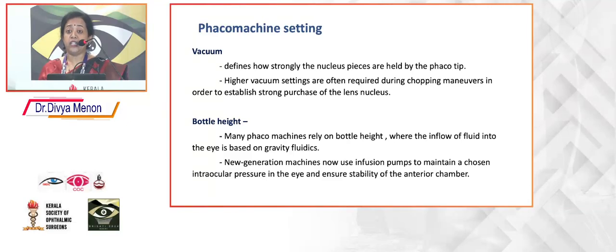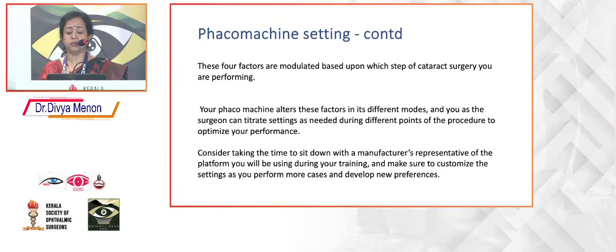Vacuum defines how strongly the nucleus pieces are held by the phaco tip. Higher vacuum settings are often required during the chopping maneuvers in order to establish a strong purchase of the lens nucleus. Many phaco machines rely on bottle height, where the inflow of fluid into the eye is based on gravity fluidics. So depending upon the cataract and depending upon the eyes, you have to adjust your bottle height. Newer mid-generation machines now use infusion pumps to maintain a chosen IOP in the eye and for anterior chamber stability. So these 4 factors are modulated based upon which step of cataract surgery you are performing.